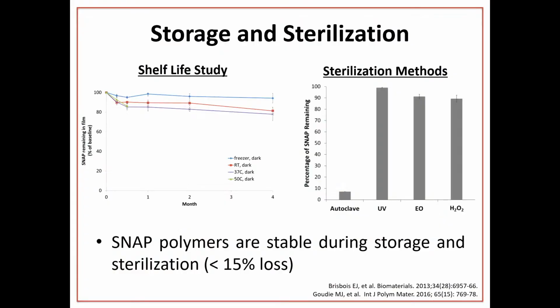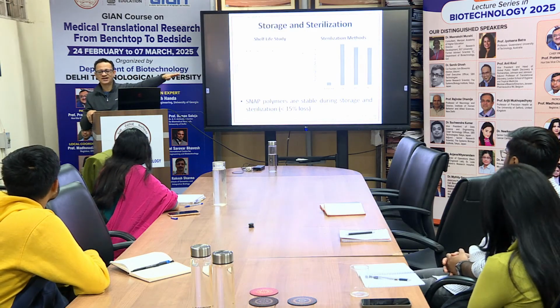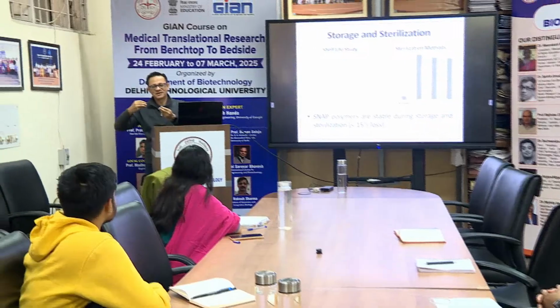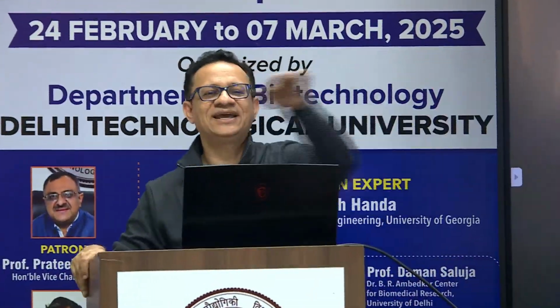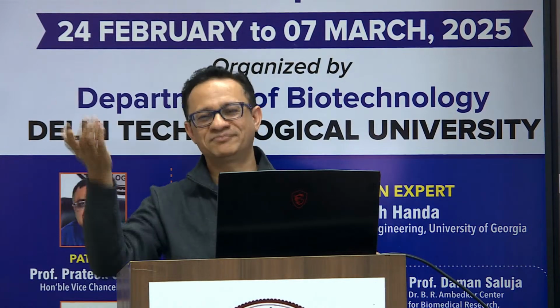Also, this study we did only to prove that, see, a catheter should be sitting at room temperature on a shelf or, let's say, in a refrigerator. But if you are shipping it, it had better reach wherever you are sending it within a week or two. Worst case, it's a month. You might lose 15% of NO, but then you can keep it in the refrigerator and you will maintain that level. It should not just be sitting at 50 degrees for 3 months. And if that's the condition, then maybe this is not the best technology.